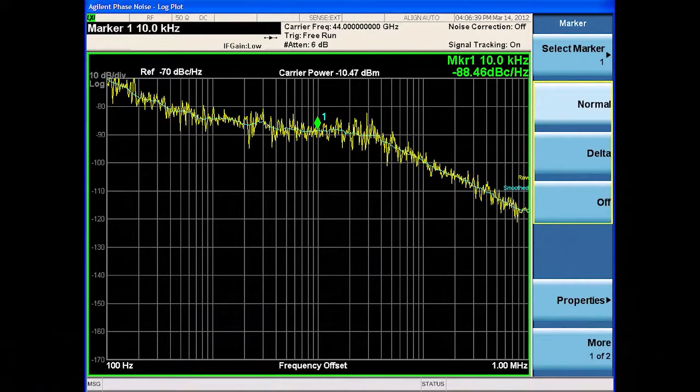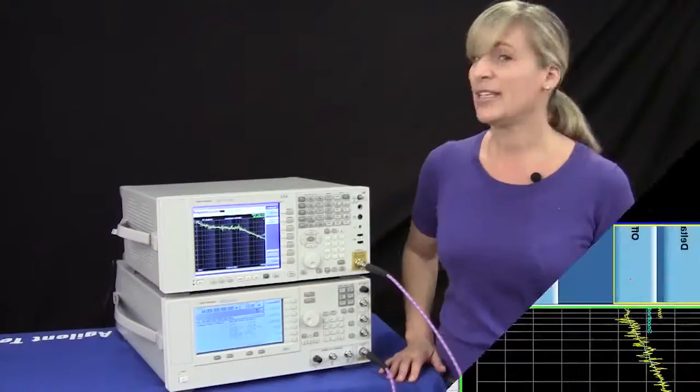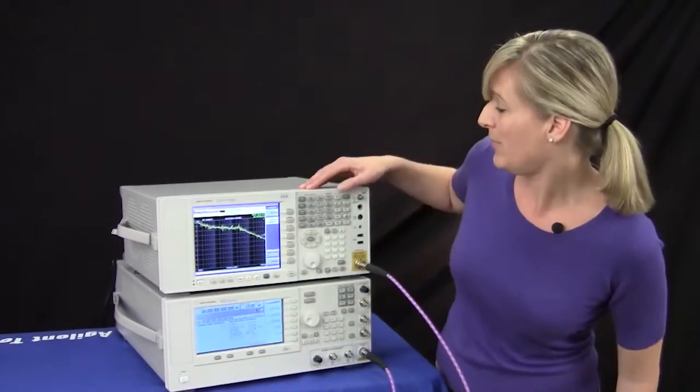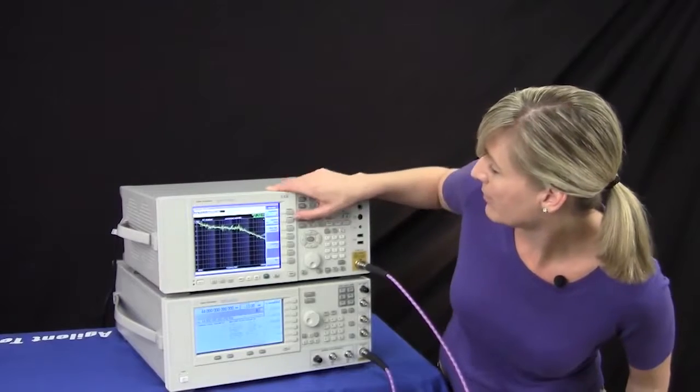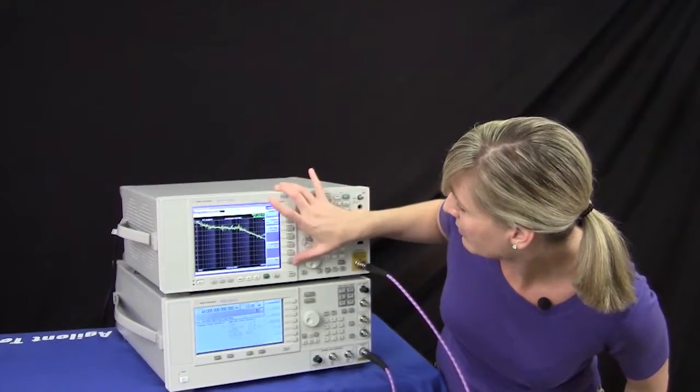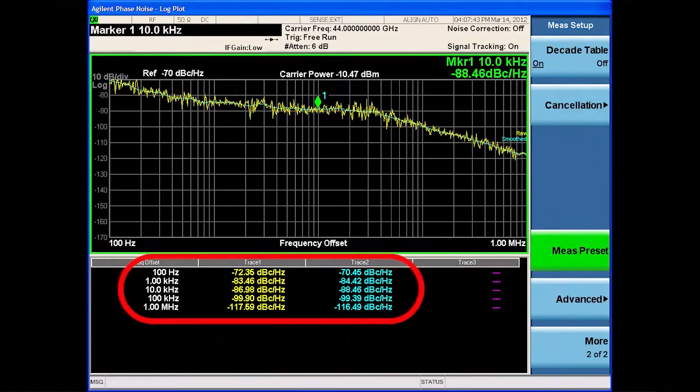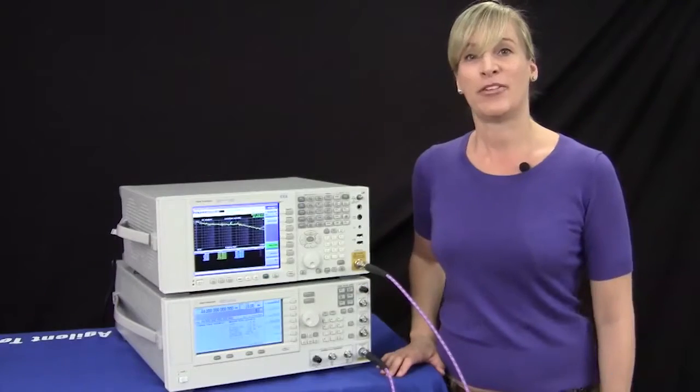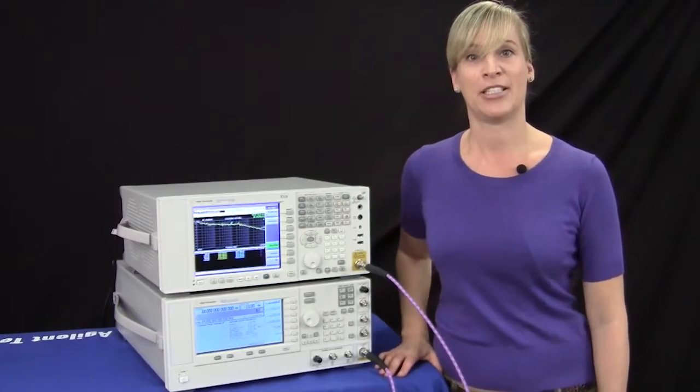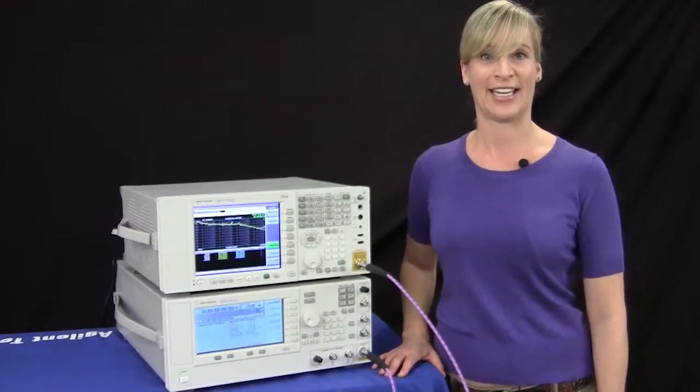This is showing you the phase noise on the log plot frequency view. It's a single sideband relative to the carrier. A marker has been placed at the 10 kilohertz offset. Within this application we also have a decade table that can be turned on and then you can view the phase noise performance relative to the carrier by decade. This is just one of over 20 measurement applications that are available on the new millimeter wave EXA.